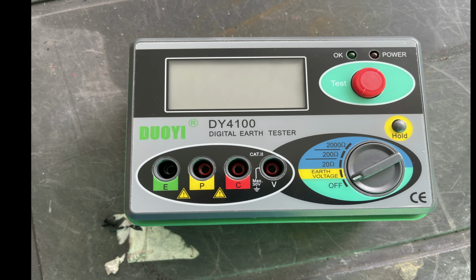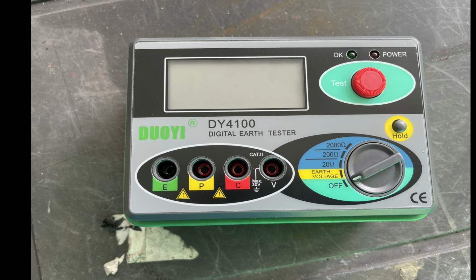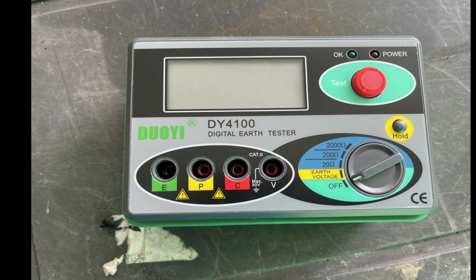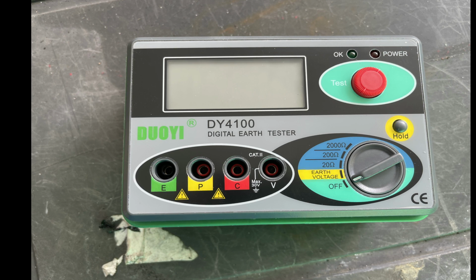The meter typically consists of a transmitter and a receiver. The transmitter generates a constant AC current, which is sent through the earth electrode and into the soil. The receiver measures the voltage drop across the electrodes and calculates the resistance.